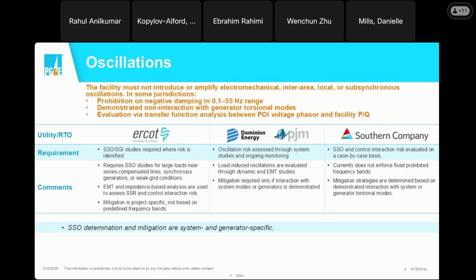In essence, I think what the oscillation requirements are really outlining is that large loads should not introduce or amplify any of the inter-area oscillation modes, local plant modes, or torsional frequencies of generators in your vicinity. Some jurisdictions straight up prohibit any type of negative damping in the 0.1 to 55 hertz subsynchronous range, which is a pretty broad range.